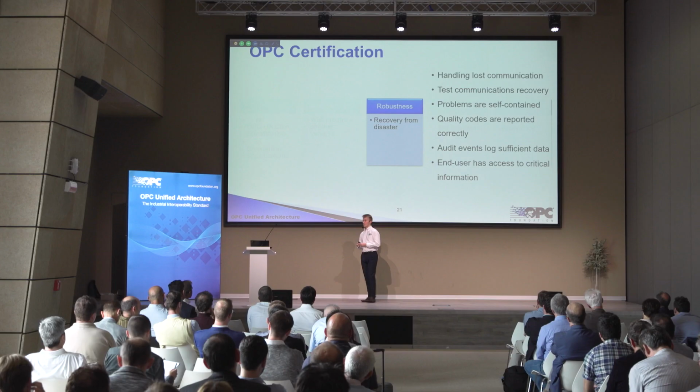In part 8, OPC UA basically describes the rules on how to map a communication state to an underlying device. So that means that the status code of a UA node of a variable needs to change to bad, no communication, for example, if the connection to the data source is broken. So that is providing all those metadata that makes OPC UA strong. And that is why we test and verify that when doing certification as well.